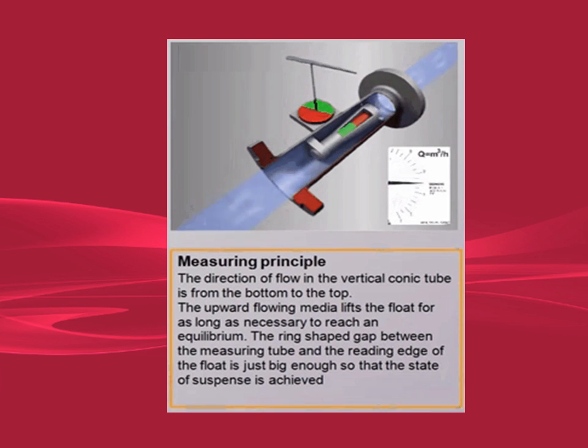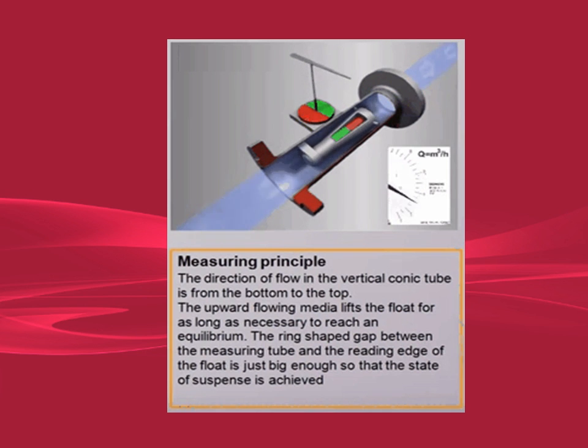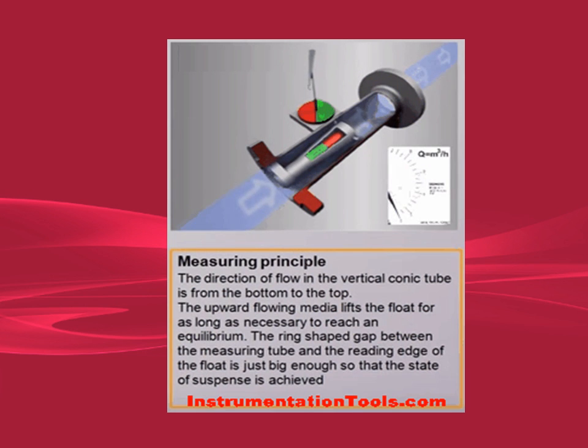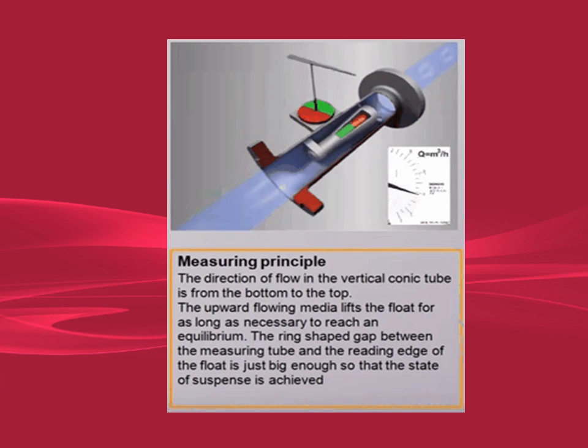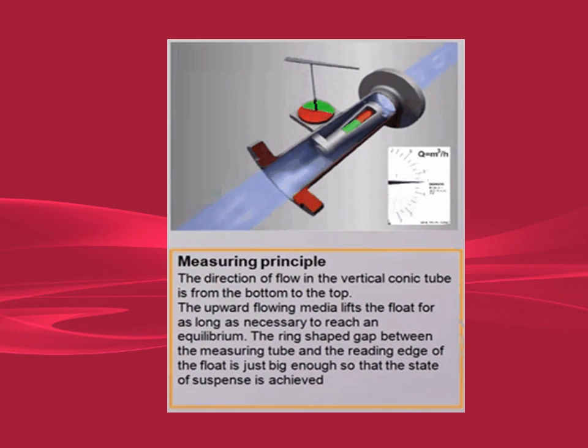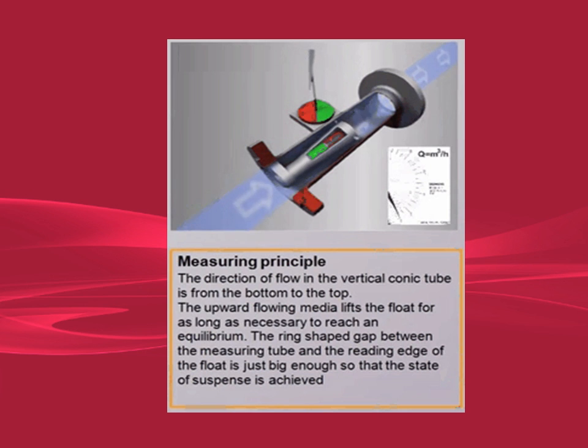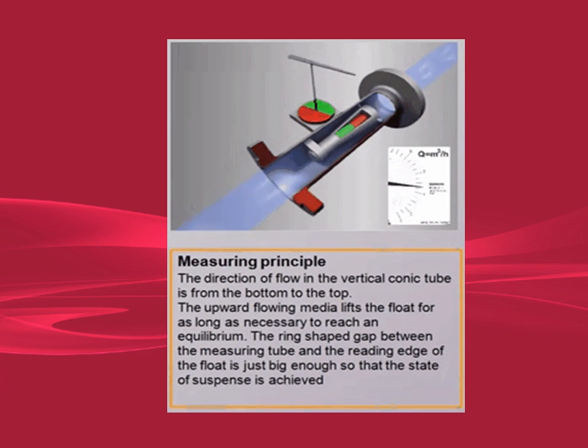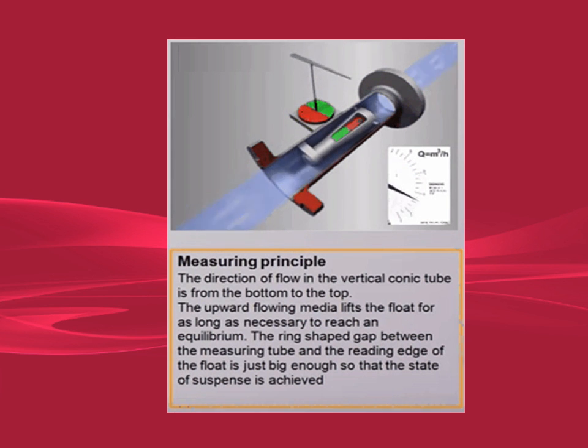The drag force for a given fluid and float cross-section is a function of flow speed squared only. A higher volumetric flow rate through a given area increases flow speed and drag force, so the float will be pushed upwards. However, as the inside of the rotameter is cone-shaped and widens, the area around the float through which the medium flows increases, and the flow speed and drag force decrease until there is mechanical equilibrium with the float's weight.